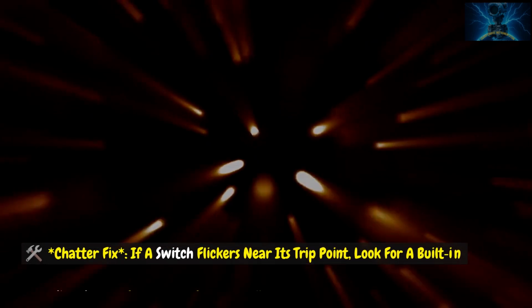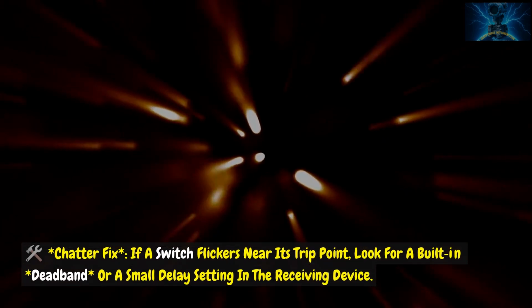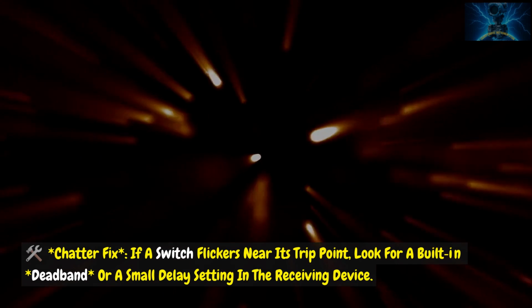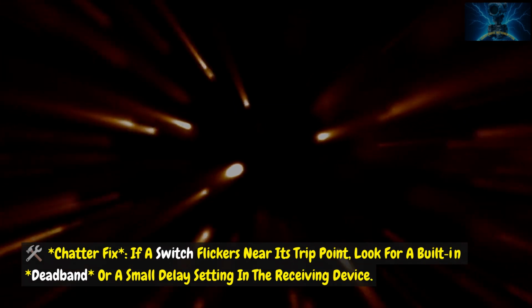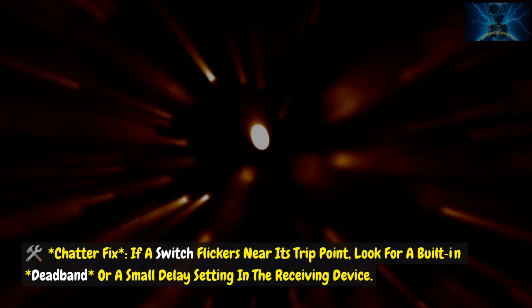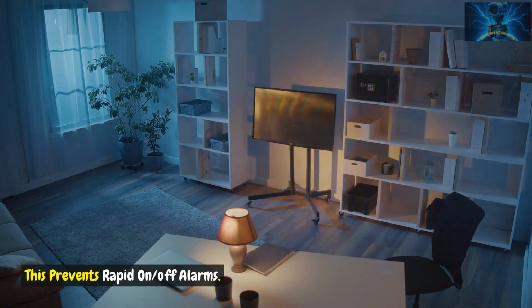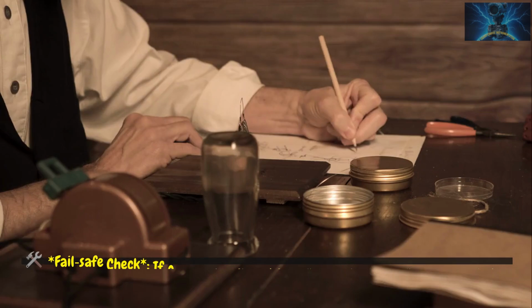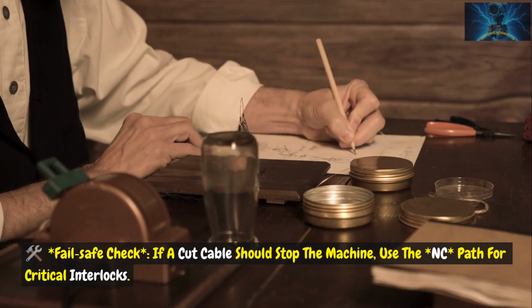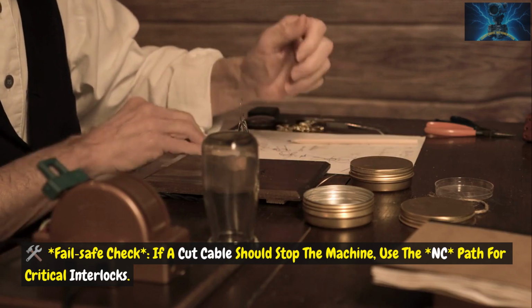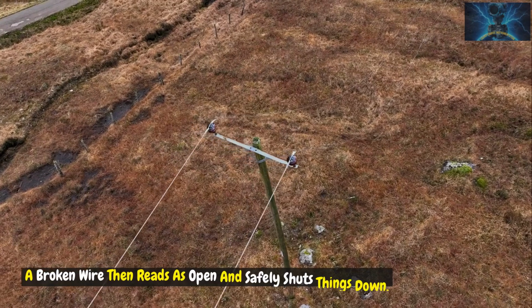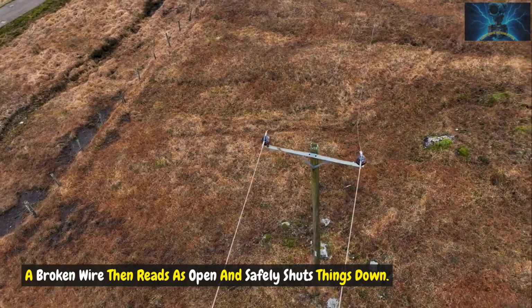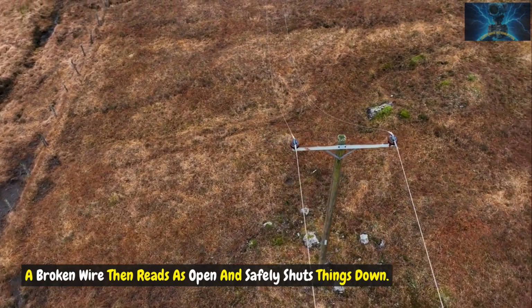Chatter fix. If a switch flickers near its trip point, look for a built-in deadband or a small delay setting in the receiving device. This prevents rapid on-off alarms. Fail-safe check. If a cut cable should stop the machine, use the NC path for critical interlocks. A broken wire then reads as open and safely shuts things down.